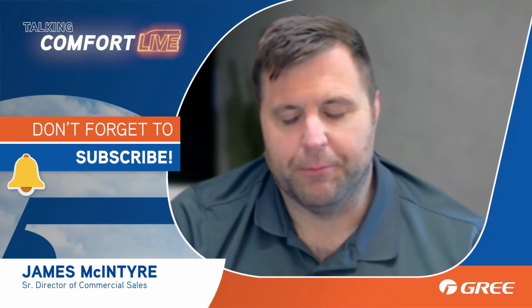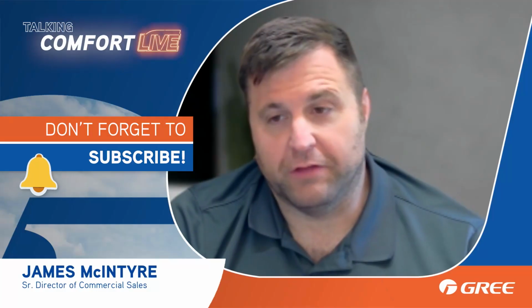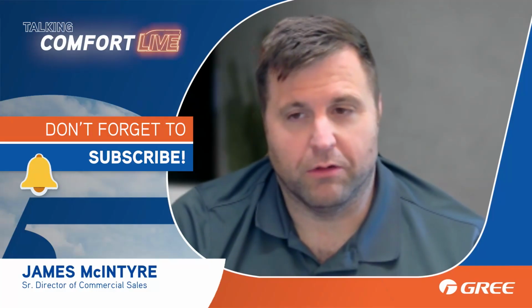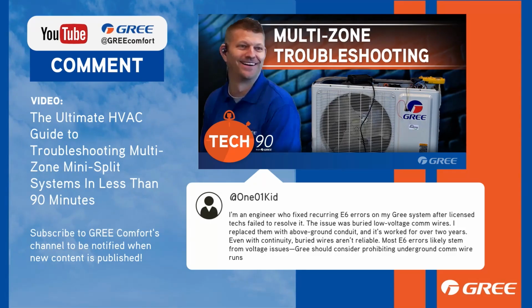How it goes into the building or whatever, we don't really provide much in the way of recommendations. But chances are, I'm going to go out on a limb and say that if that's what was part of the issue with the communication, if they had used shielded and grounded that shielding at the outdoor unit only, they might have been able to bury that cable and use that cable as is.